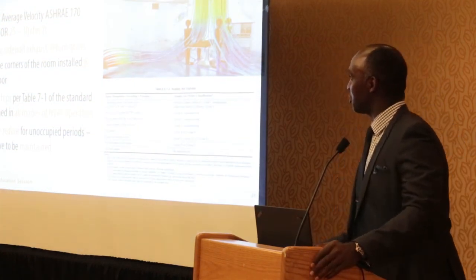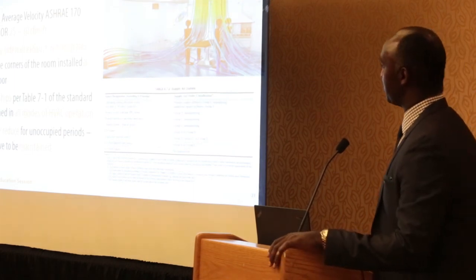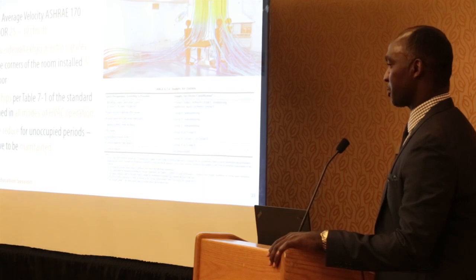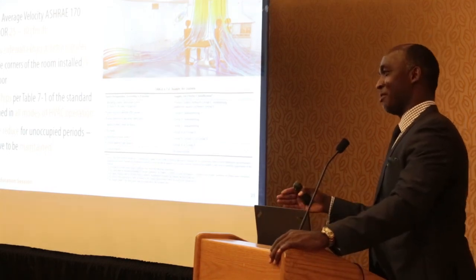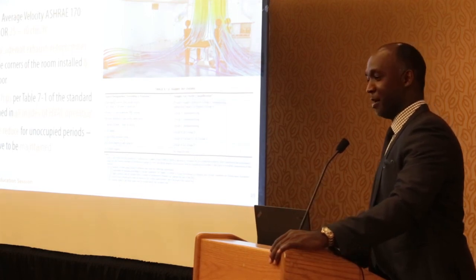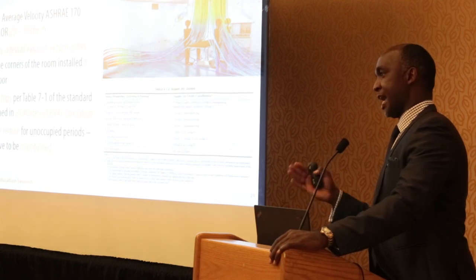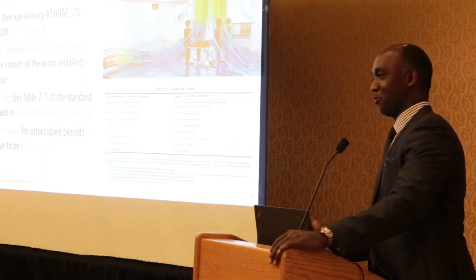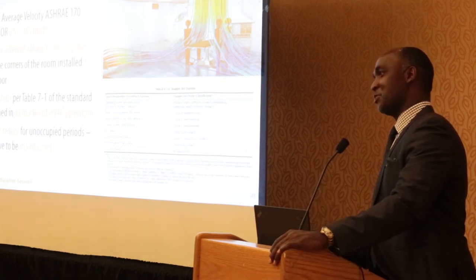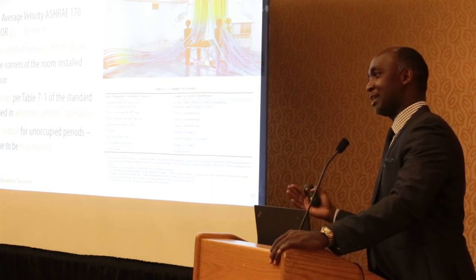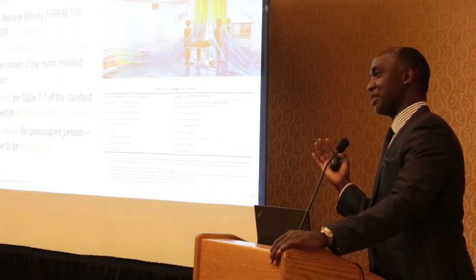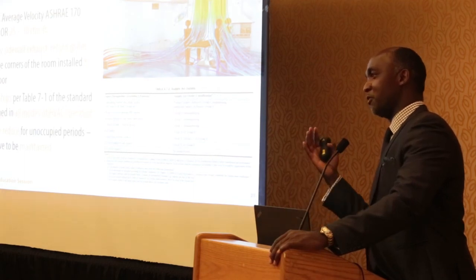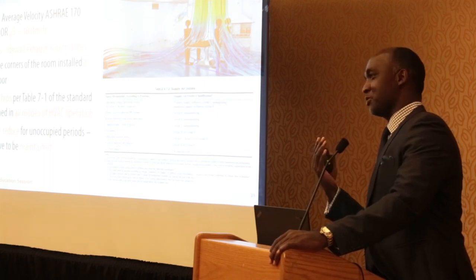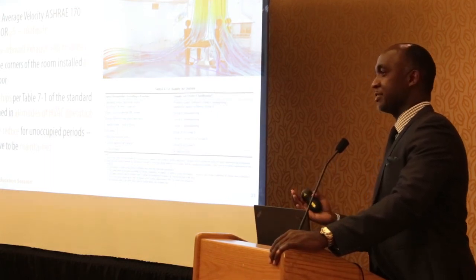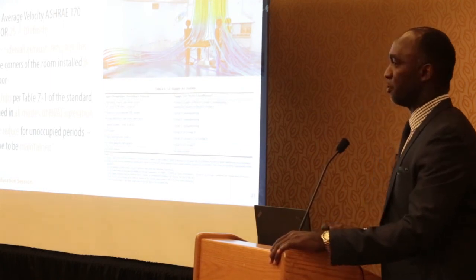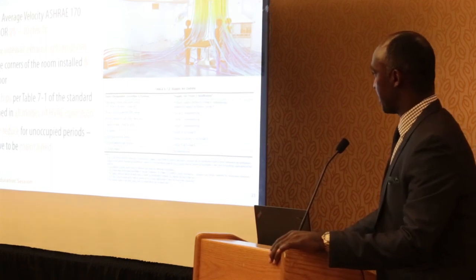Looking at air distribution, one set also talks about 25 to 30 CFM per square foot. One of the other requirements is that you require 2 low exhaust or return grilles within the space. Even in USP 800, which is the requirement for labs and pharmacy, you have to have low diffusers. And this has to do with entrainment. It's to do with the direction of air, making sure that when you have air passing over your patient, it follows the path of least resistance to get out of the space and back to your air handling units or wherever you want it to be. That's the reason why they have it at the lowest point. And this has been proven using CFDs and also smoke tests within the space.